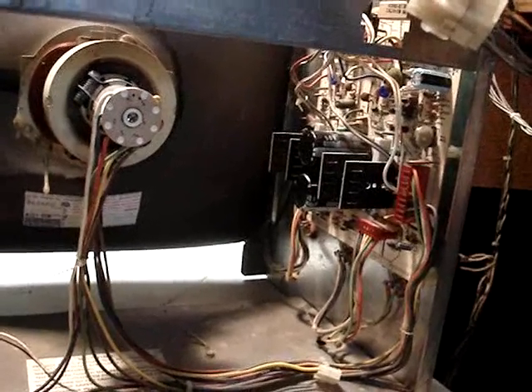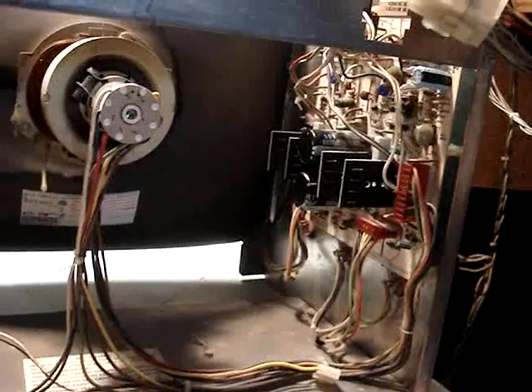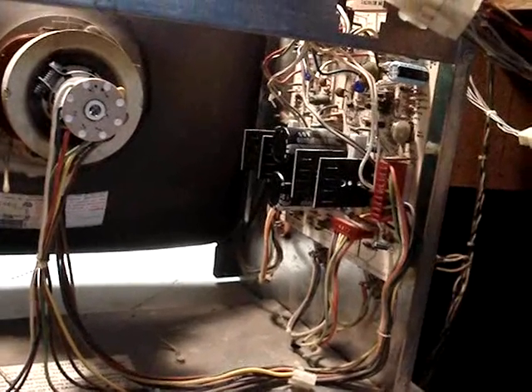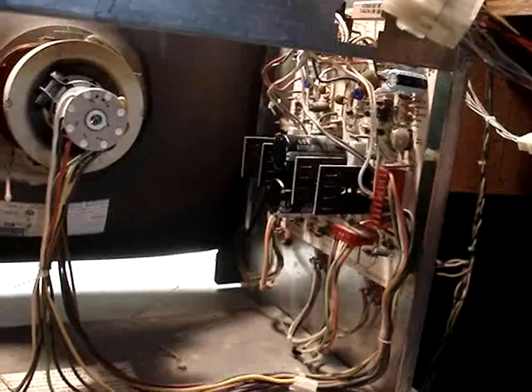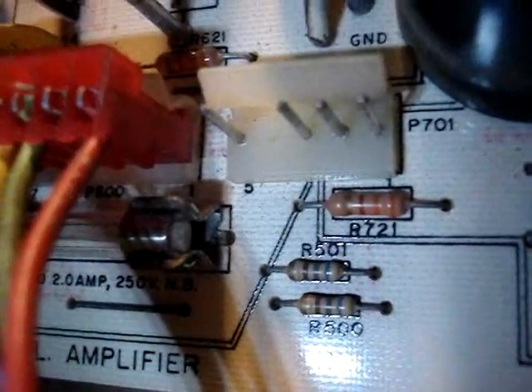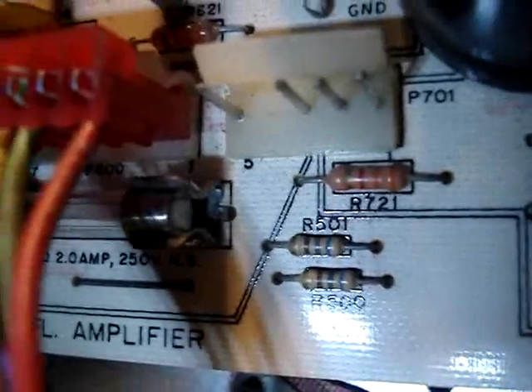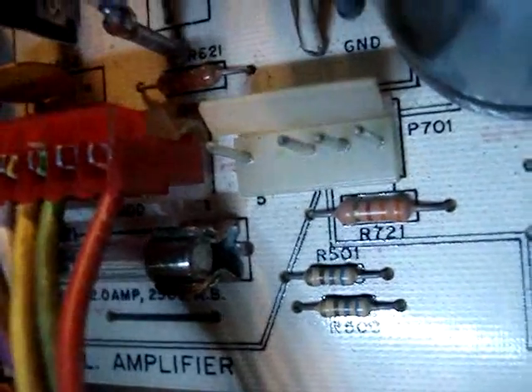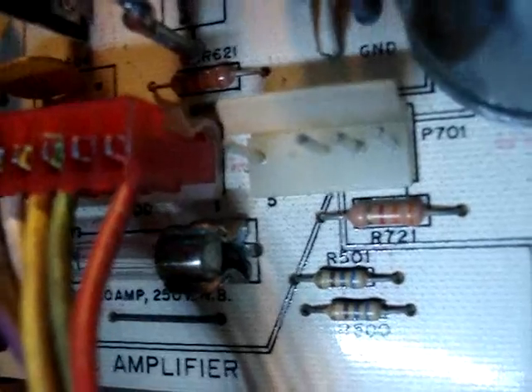So I got looking and reading in that document, it says that sometimes people change it at the monitor rather than the harness. So I got to looking, and it says you're supposed to reverse pins 1 and 2 on P700. Well, that's the only mistake in the document. If you look at this, that's P701. But they got the information correct. Pin 1 is on the right-hand side.